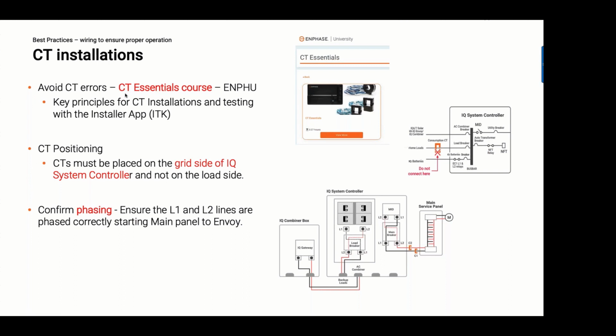The first best practice recommendation is to review some of the key basic CT installation principles. You can do this through the CT Essentials course in Enphase University. This online short course covers 95% of the errors made in installing and wiring production and consumption CTs. There are 3 lessons in the course, which take about 15 minutes in total to go through, and well worth it, I think, if it will help you avoid an error. Otherwise, you'll have to go back and fix a problem on site later.